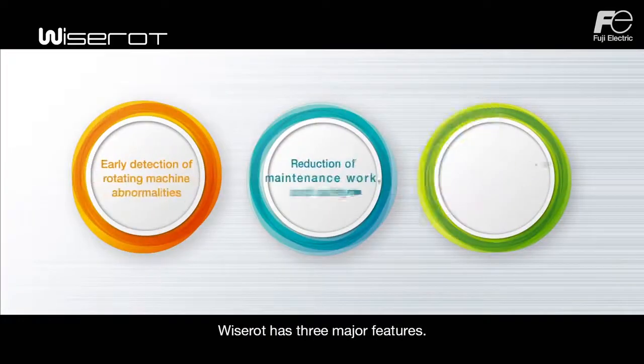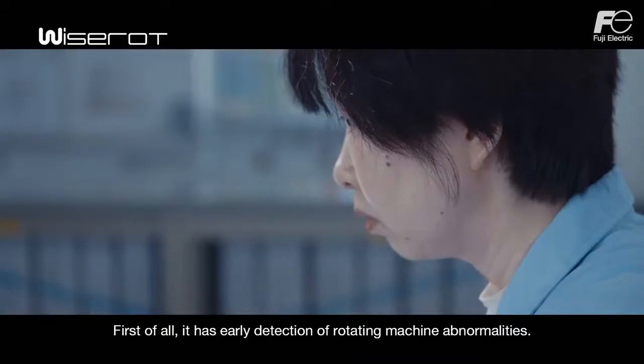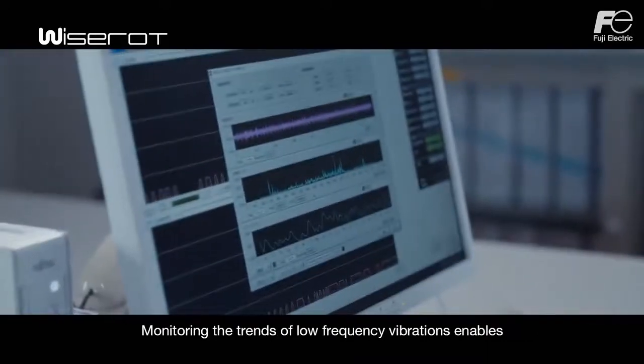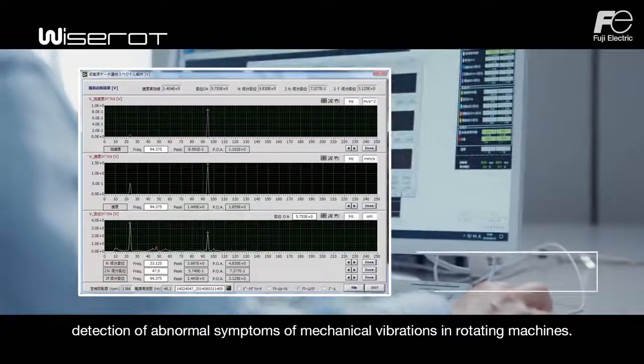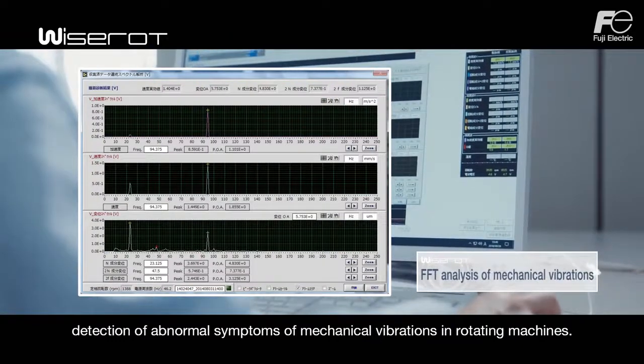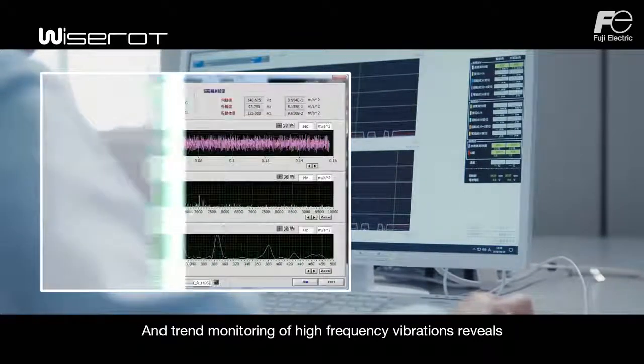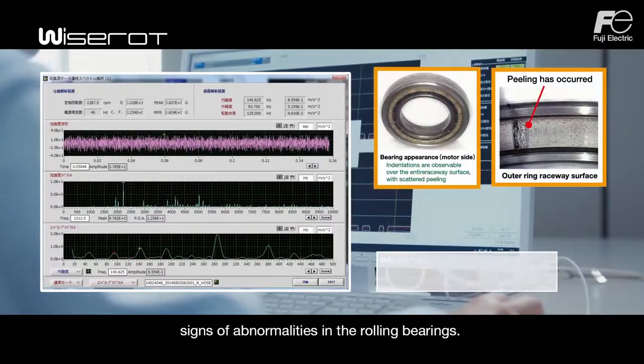Wiserot has three major features. First of all, it has early detection of rotating machine abnormalities. Monitoring the trends of low-frequency vibrations enables detection of abnormal symptoms of mechanical vibrations in rotating machines, and trend monitoring of high-frequency vibrations reveals signs of abnormalities in the rolling bearings.